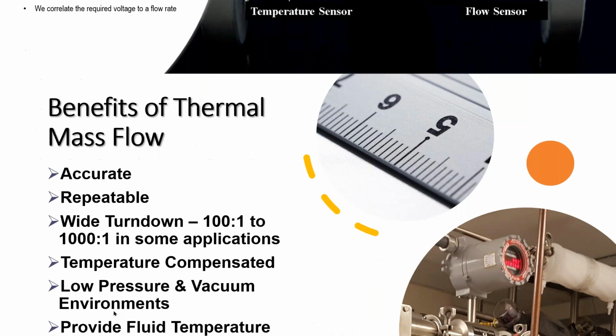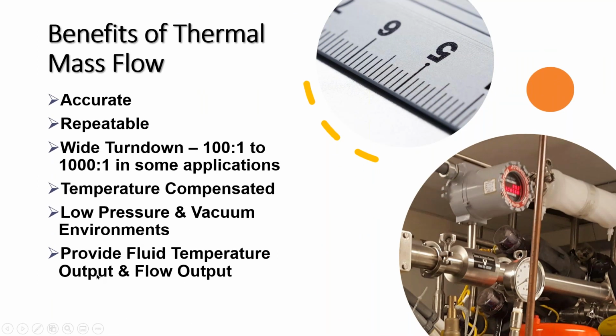Let's talk a little bit now about some of the benefits of using thermal mass flow. For one thing, thermal mass flow is very accurate. Typically, we're plus or minus 1% of full scale in most situations. The reason we can be accurate is our sensors really never come into direct contact with the fluid, and typically cannot be fouled by any foreign substances that would degrade the sensitivity of that sensor. So we can give you very accurate measurements for many years.